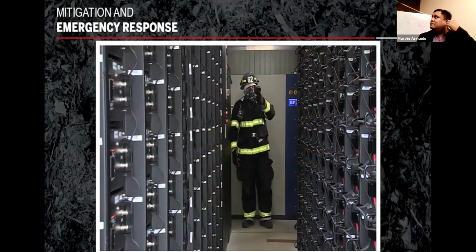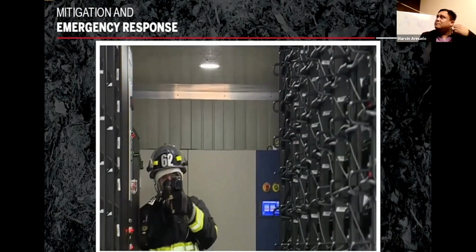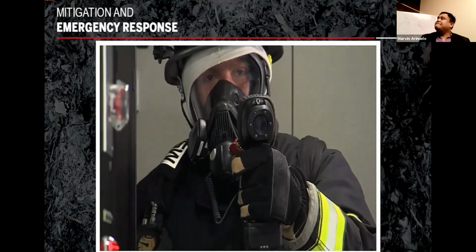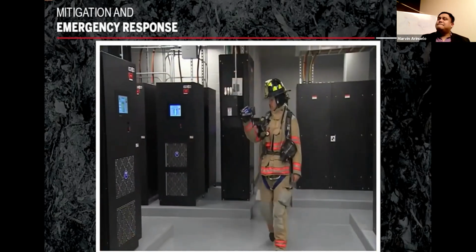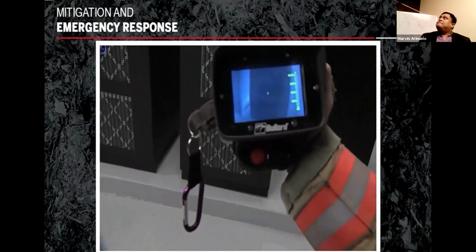If there was a fire involving the BESS, continued monitoring for reignition is imperative. Studies have shown that this can take hours or even days to occur. In certain circumstances, a thermal imaging camera can be a helpful tool in the continuous monitoring for temperature changes.